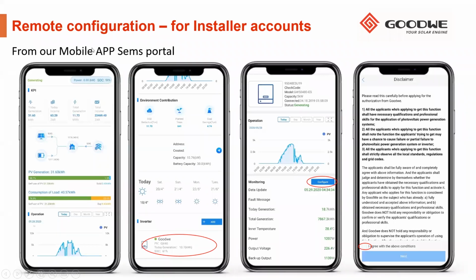Then you can just open your mobile phone app. You select your plant. You scroll all the way down to the bottom and you'll see your inverters on your plant. Select the specific inverter, because you can only do one inverter's configuration at a time. It will open up to the inverter information and you'll see the blue configure button. You press the configure button, read the terms and conditions and agree.